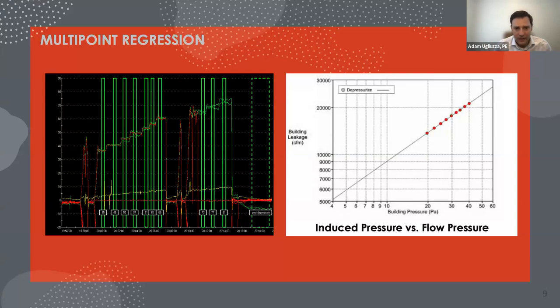Like I said, in commercial buildings, multi-point is really what's being used. 2-point, there could be an argument for that, but if you're doing 2 points, you're already on your path to do multi-point, and multi-point's just much better. There's more data points, there's more accuracy, and over time, as we've done this test and we've seen how the data is produced through high wind conditions, different building types that may respond to wind differently than others, the more data points you have, the more accurate the test. And that's really why multi-point regression has been adopted as the test that needs to be done.